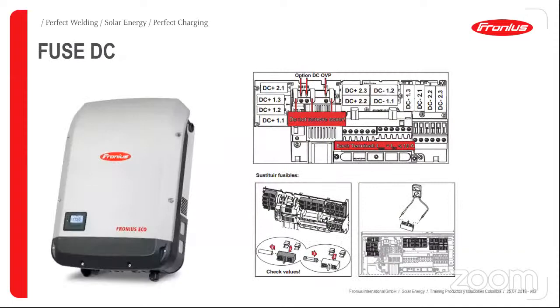In some of our inverters, we also can put fuses inside them. So this is allowed for the bigger inverters. In the Primo references, it can be put inside the inverter from 15 kilowatts, from 8.2 kilowatts, and in the Symo from 15 kilowatts to the biggest ones. In the Tauro, this is ready and is installed in all the inverters.